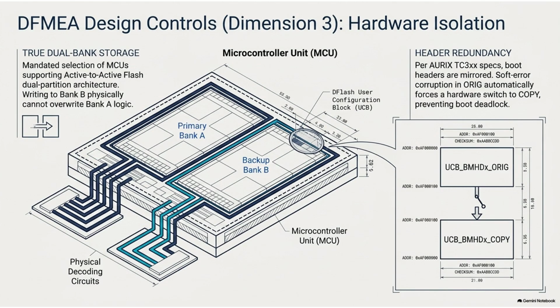If the cabinet burns down, both folders are gone. Precisely. To prevent this, the EV design specification mandates microprocessors that feature physical active-to-active dual bank flash, meaning Bank A and Bank B are completely separate pieces of silicon real estate, physically distant from each other on the die.